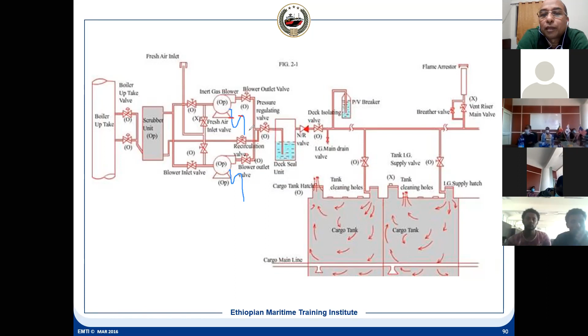So once you start this, then you monitor the O2 content. Once the O2 content is within the limit, then you can send the IG to the tank. Because if O2 content is more than 8%, you won't be able to start your cargo pump, because it is interconnected. Cargo pump you will be able to start only when your O2 content is less than 8%. And then you can send the IG to the tank.